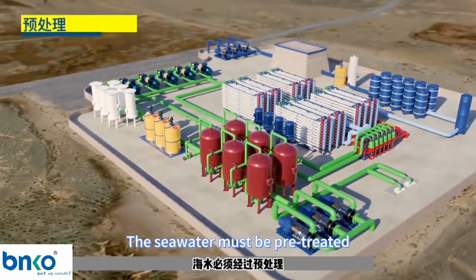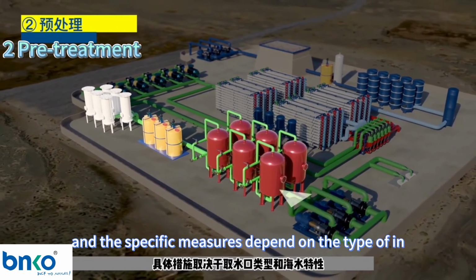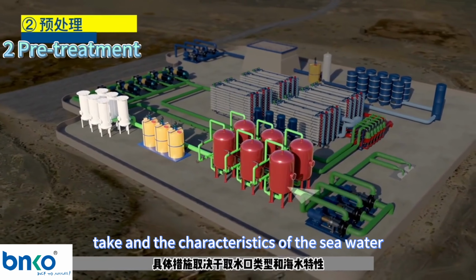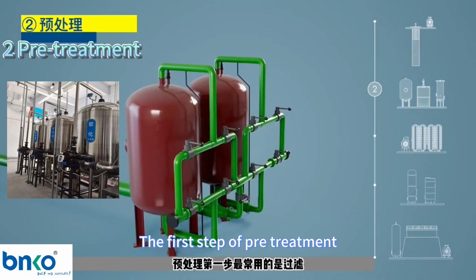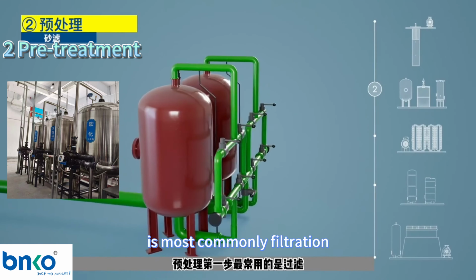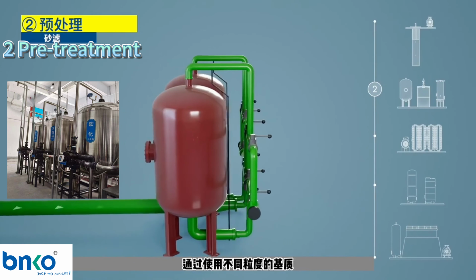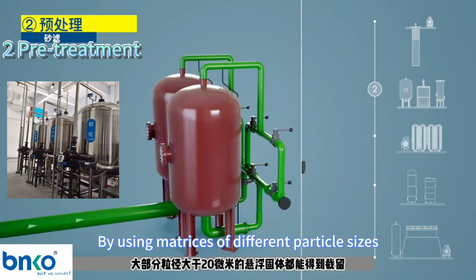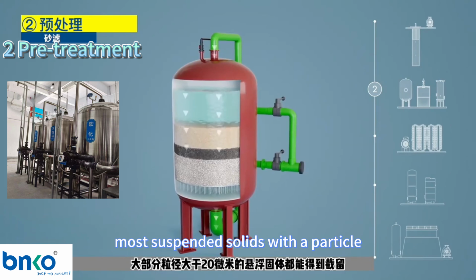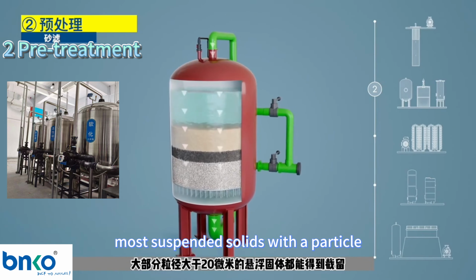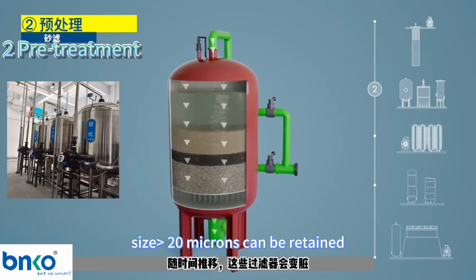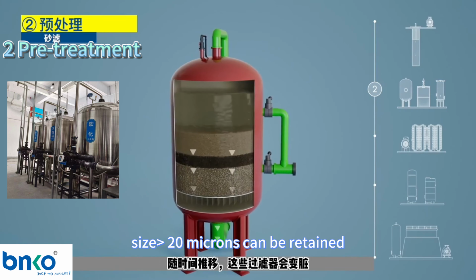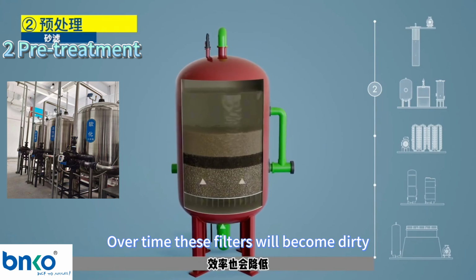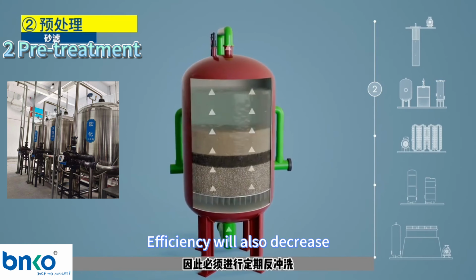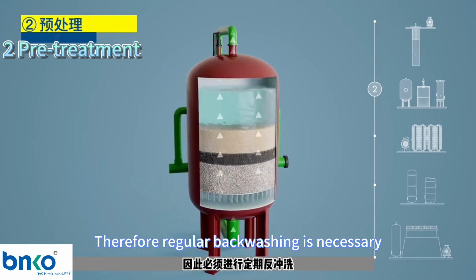The seawater must be pre-treated, and the specific measures depend on the type of intake and the characteristics of the seawater. The first step of pre-treatment is most commonly filtration, by using matrices of different particle sizes. Most suspended solids with a particle size greater than 20 microns can be retained. Over time, these filters will become dirty. Efficiency will also decrease. Therefore, regular backwashing is necessary.